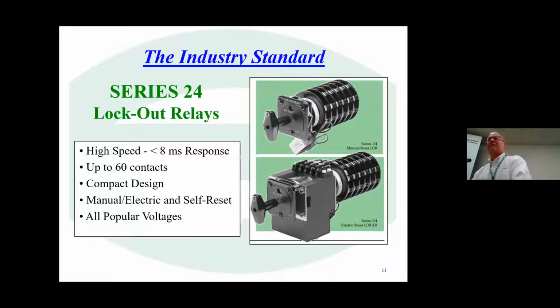substation transformer, you don't misoperate it or switch a control into a faulted transformer. You want to make sure you send somebody out there and troubleshoot the problem for it to trip before you enable the controls back on the system. So the Series 24 lockout relay for Electroswitch is the fastest in the industry, and we've designed it to have up to 60 contacts available to do switching.